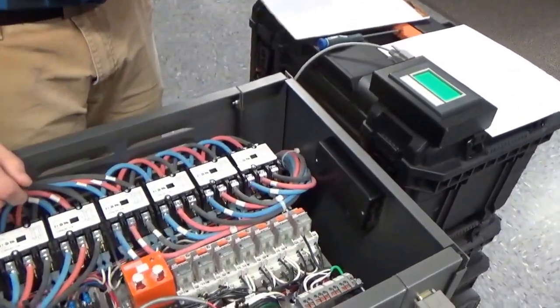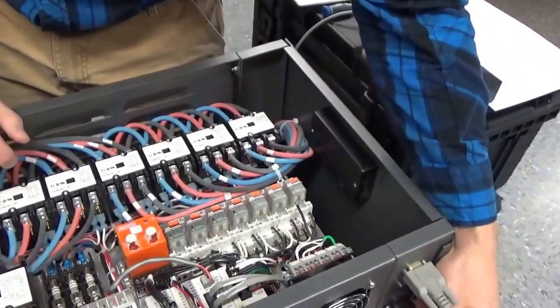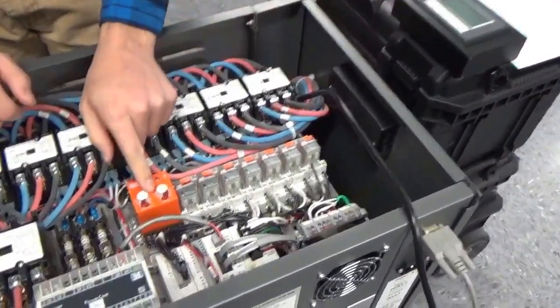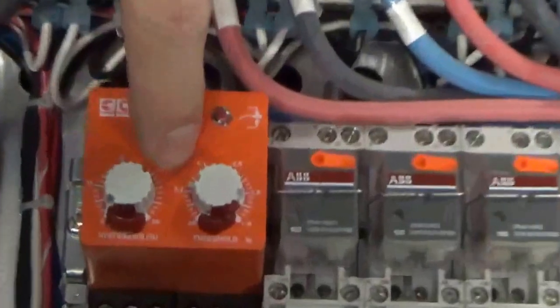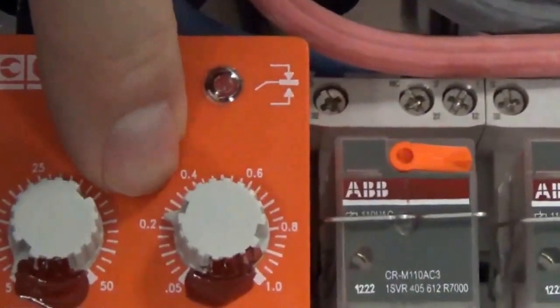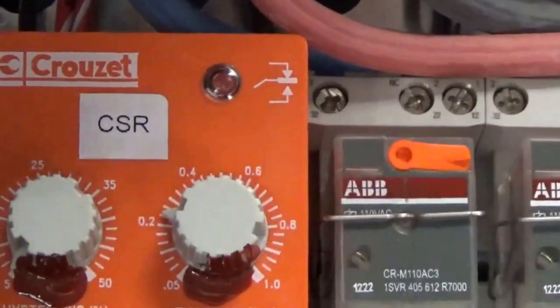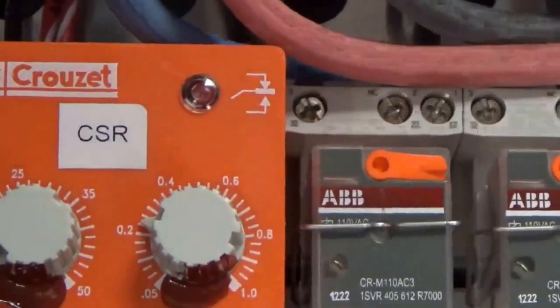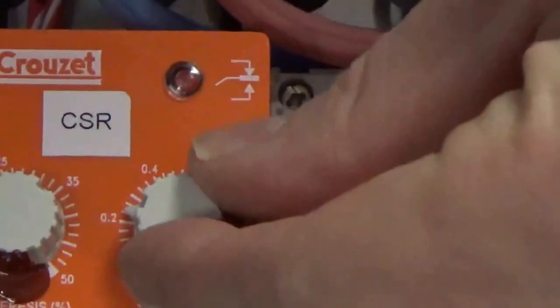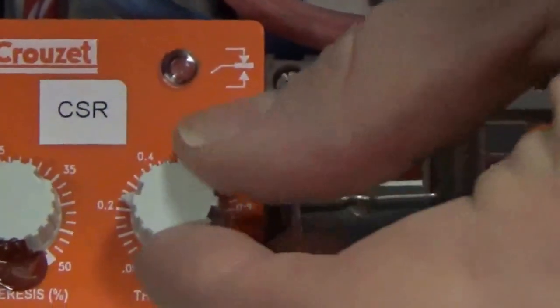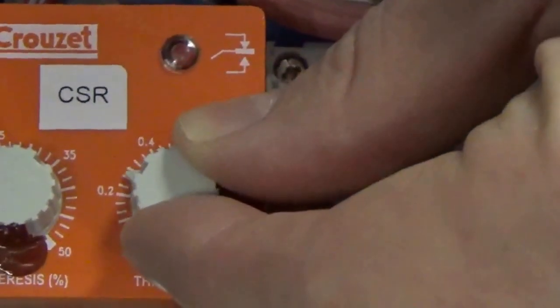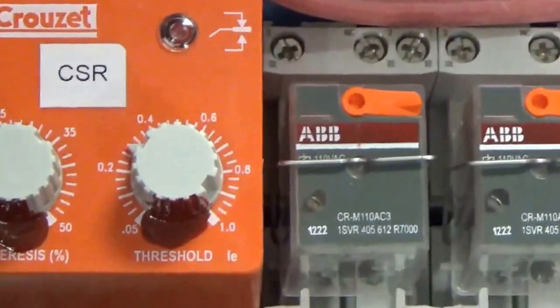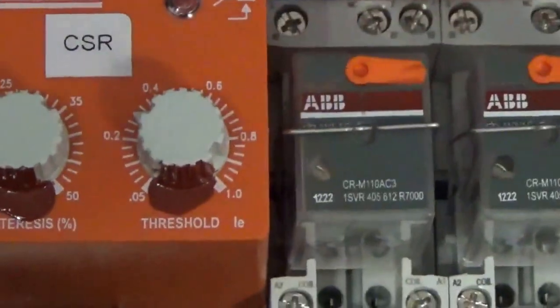Now, what we want to do is remove control power and find the range in between those two points to set the threshold. So remember, I was at 0.36 with four fans and 0.23 with three fans. That's going to average out to 0.3 right there. Once that's set, we can plug our fourth fan back in.